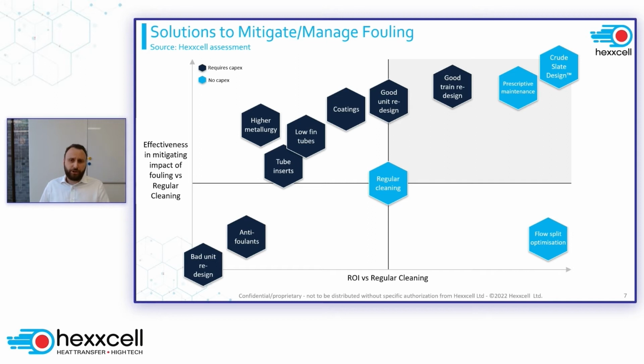We have some options, including redesigning the heat exchanger, or using technologies such as coatings, low fin tubes, and tube inserts. But all of these technologies need capital, and we also need to stop the plant to implement them. Their ROI can be lower than expected, especially since coatings might extend the time between cleanings, but regular cleaning will still be required. So most of these technologies, while they may reduce fouling, will still lead to some sort of cleaning at some point.